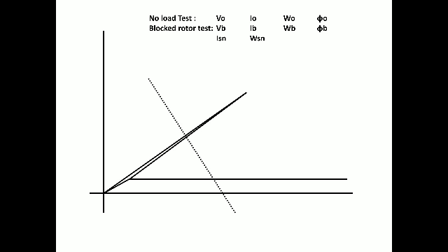So by making this point, you can draw the semicircle. Actually, it is not a semicircle, but while drawing, you get a neat semicircle. Now, after the semicircle, you get the point at the top portion of the output line. From that point, you have to draw one vertical line. This vertical line should be considered as the losses. This is the total loss of the machine. Here, the upper part is considered as the copper loss, and the lower part is considered as the fixed loss. In fixed loss, iron and mechanical losses are clubbed.